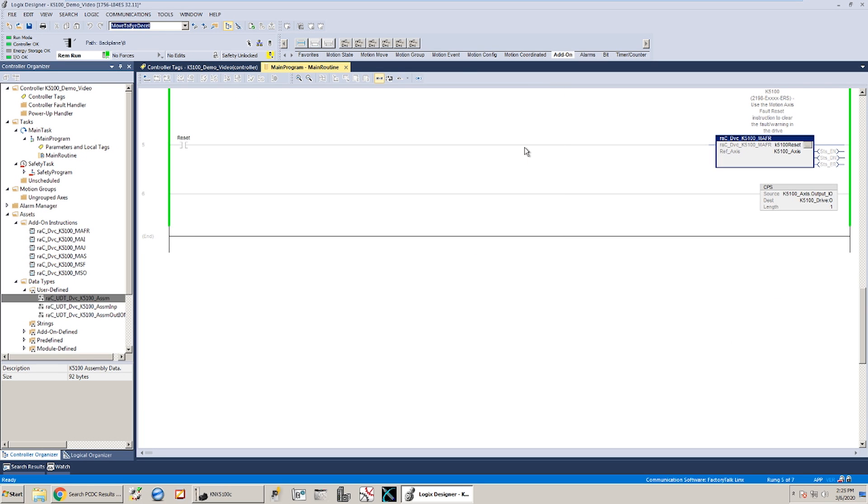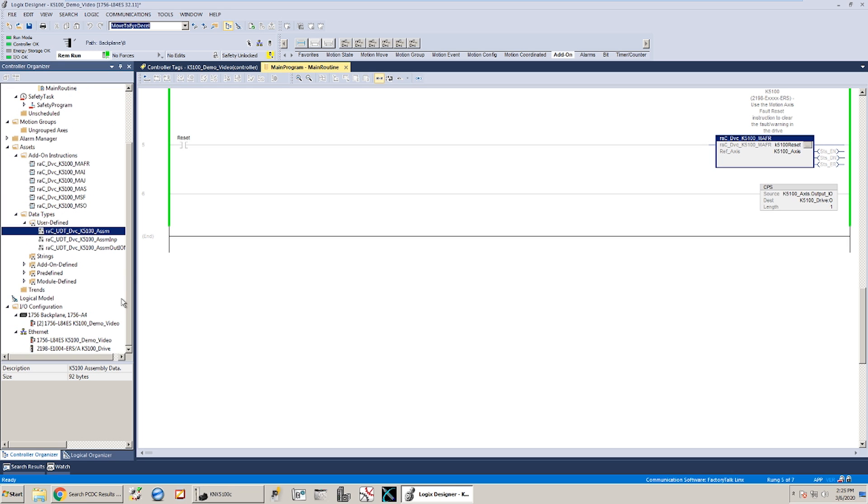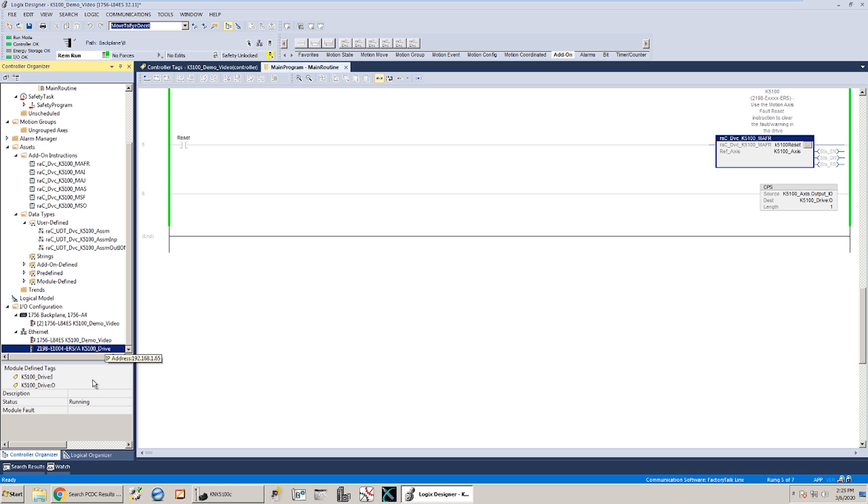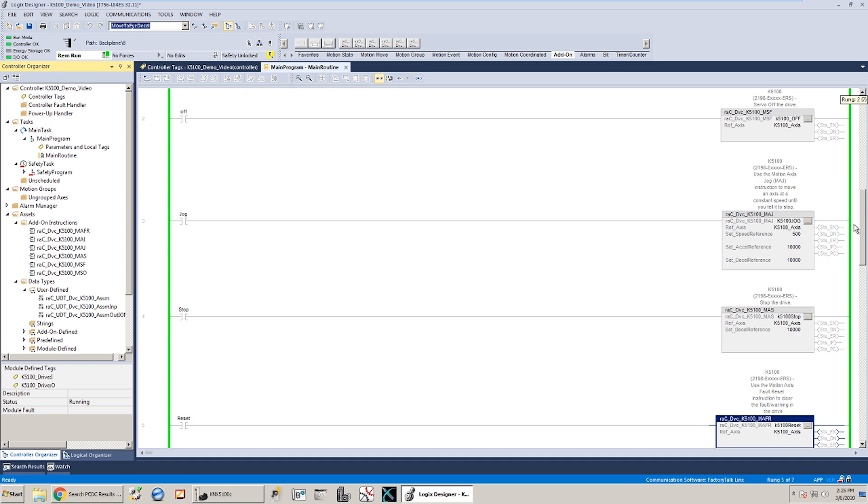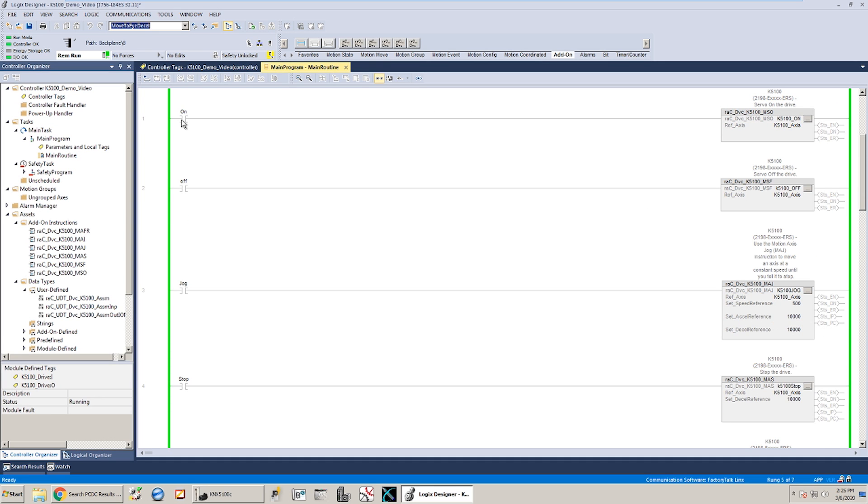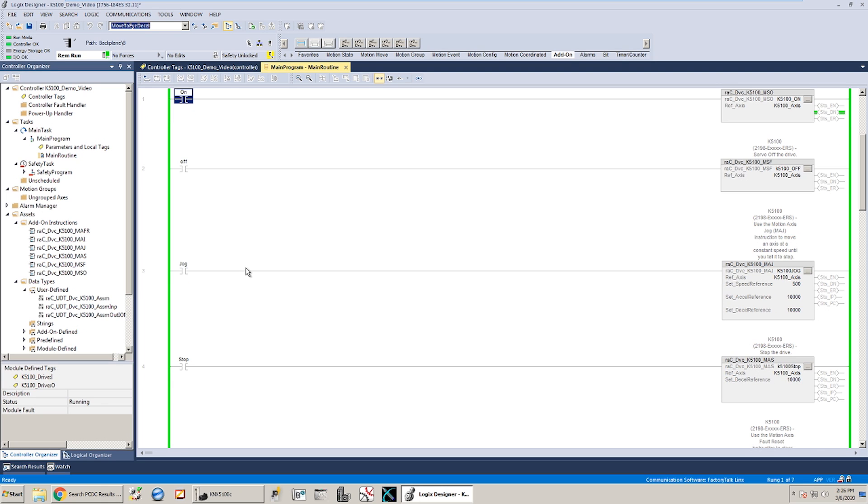Alright. So our download is complete. My IO OK light is solid green. That's a good sign. The drive down here says it's running, which means we're up, we're communicating. And if I come to my motion servo on, give that a toggle, looks like it took effect. And the motor is enabled. You don't need to hold that bit on. Once it's got a motion servo on, it'll stay on until you turn it off, or it faults out, or it loses power. Any of those scenarios.